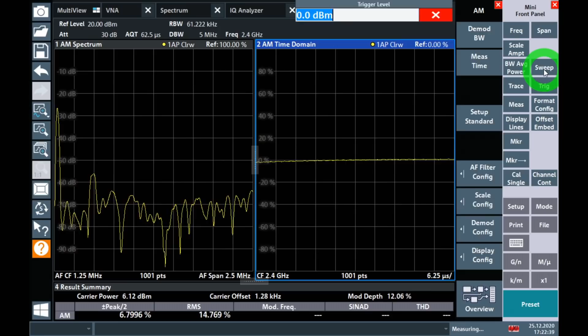Now we're going to configure this a little bit so that it's more suitable to the kind of signal we are looking at. Let's go ahead and change this time signal here. Let's go under sweep. Let's say I want to look at a 5 millisecond signal like before. There it is. Here's our signal. And now that we have it, we can go to trigger, and trigger on AM at 0%. Perfect. Look at that. That looks quite nice now. So here's our AM signal. It's giving us the frequency of the AM signal, which is what we were expecting, about a kilohertz. It's also giving us the THD, which is minus 31 dB, which is not that bad actually.